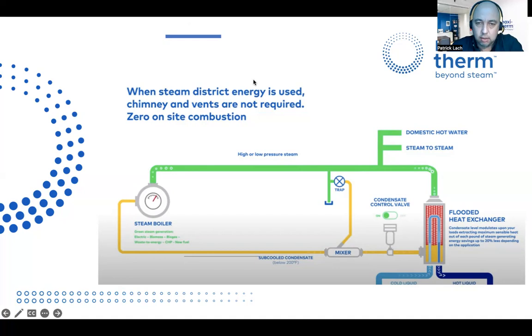In our case, we can directly use high-pressure steam coming from the grid, 175 PSI steam, so no more pressure-reducing valve creating more heat, because there's superheat generated after a PRV. I did a lot of walkthroughs over the years in different buildings in New York, and some of them are pretty hot in that mechanical room, mostly because of the PRVs, pressure reducing valves. So we don't need those. We're coming in at 175 directly on top.